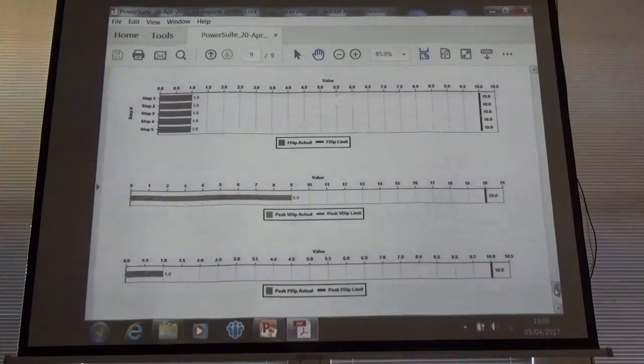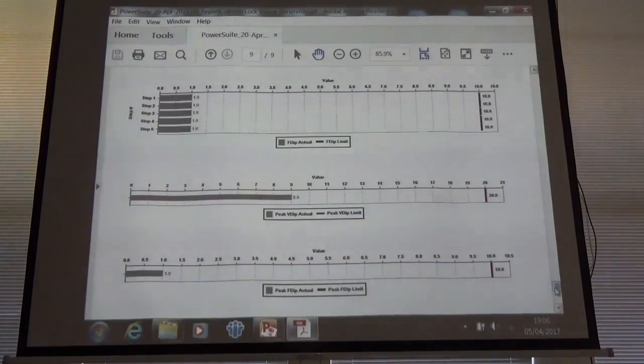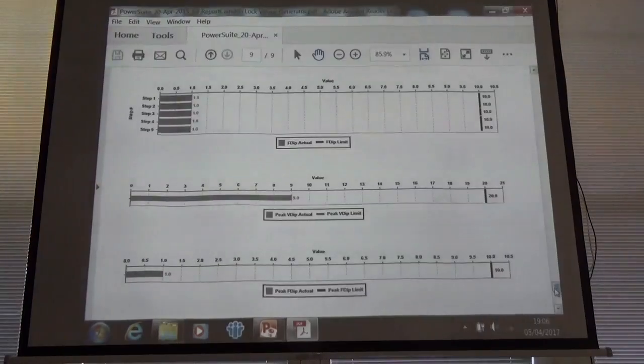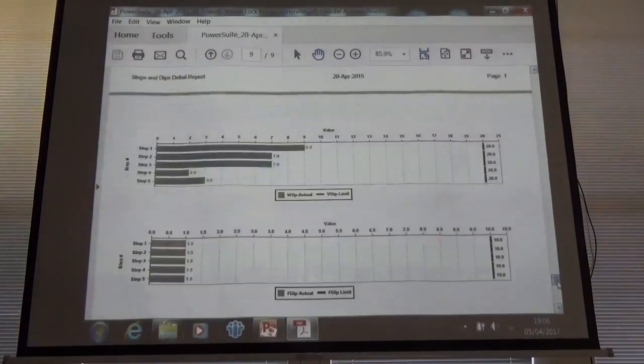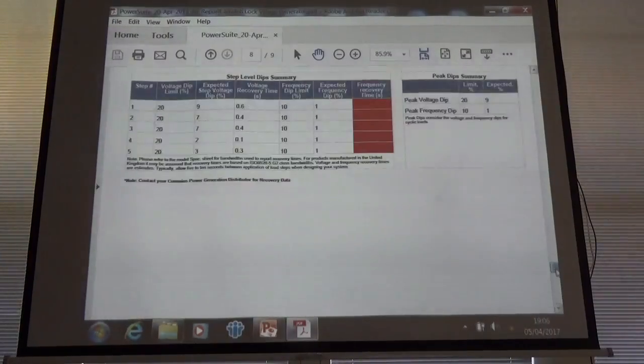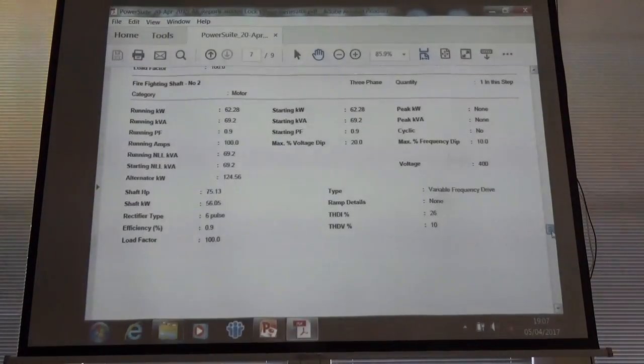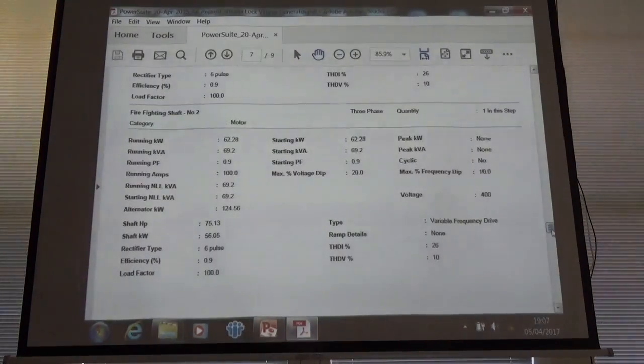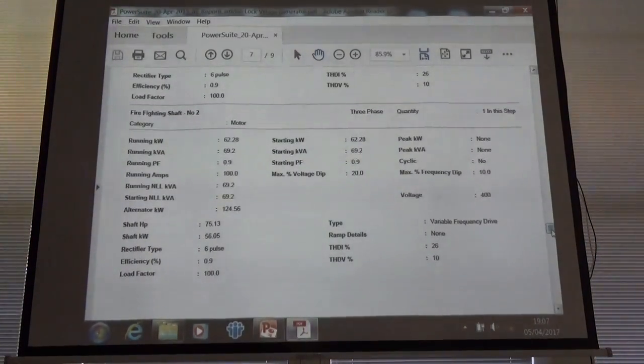So you can see, you set the parameters on these software programs, it can give you very much an idea, and it'll also break down all the starting loads, everything that engine's going to see throughout the steps. So it gives you the full motor breakdown, the shaft kilowatts, it assumes losses through that, so you know what electrical input you need to give you the 55. What size is this? Yeah, 55, this one is a kilowatt motor, I think.